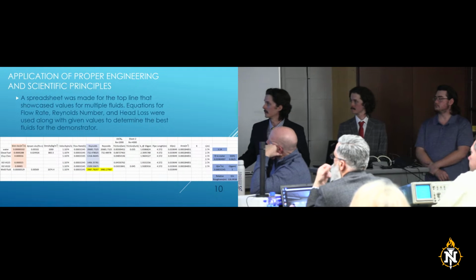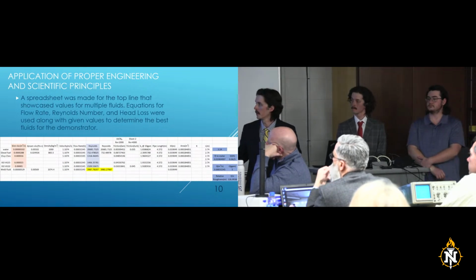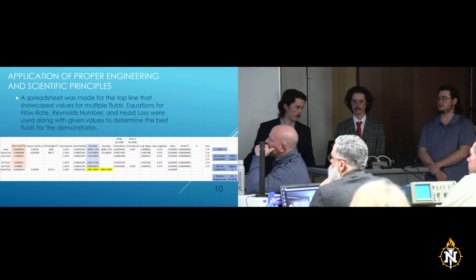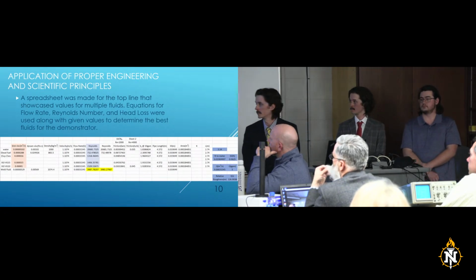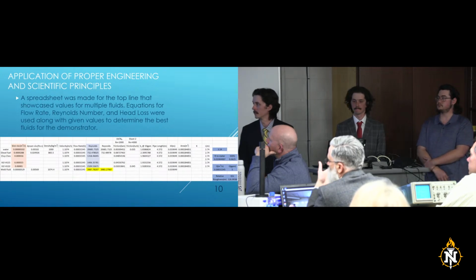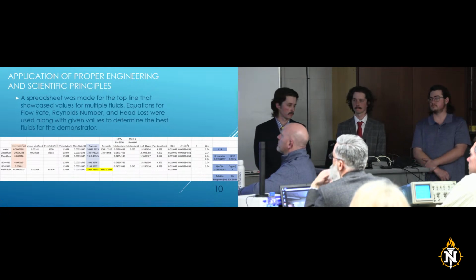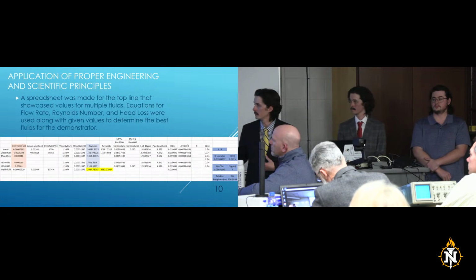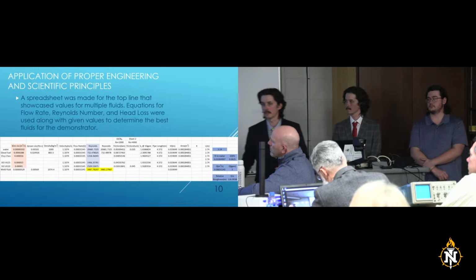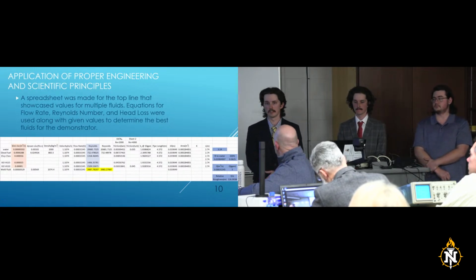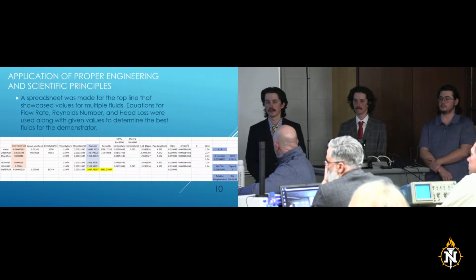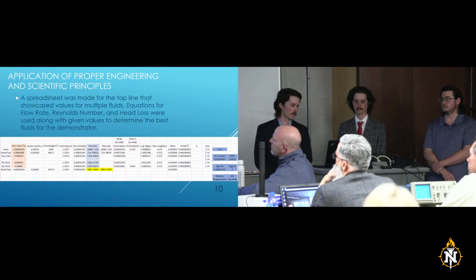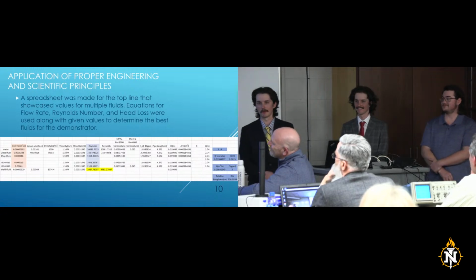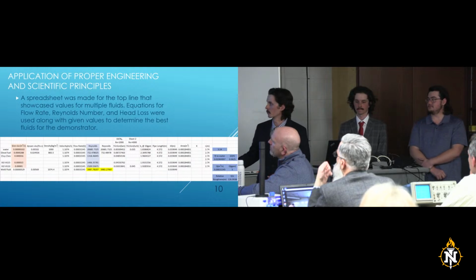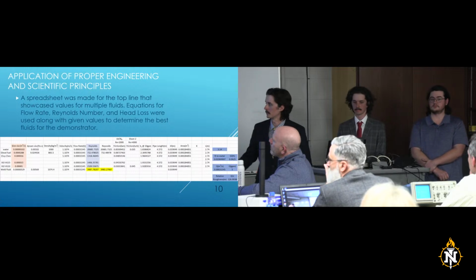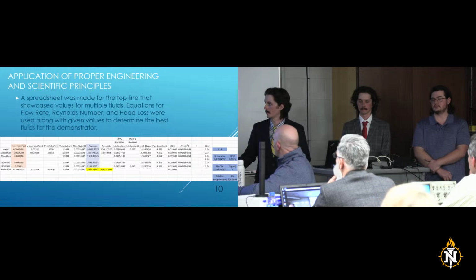The viscosities we used on this line were found on tables online. Water has a viscosity of 0.001, which is 1 centipoise. So we were looking for a hydraulic fluid somewhere in between the Ricon that we used and the water that we are currently using. And Cale offered a fix with this weld fluid here. I couldn't find the viscosity for that fluid, but I looked up online that it is a 50-50 mixture of deionized water and ethylene glycol, which gives us a viscosity of about 0.005, which is about 5 centipoise. Then at 5 GPM, we're right in the transition zone at a Reynolds number of 3,900, which is about 10 underneath turbulent flow.